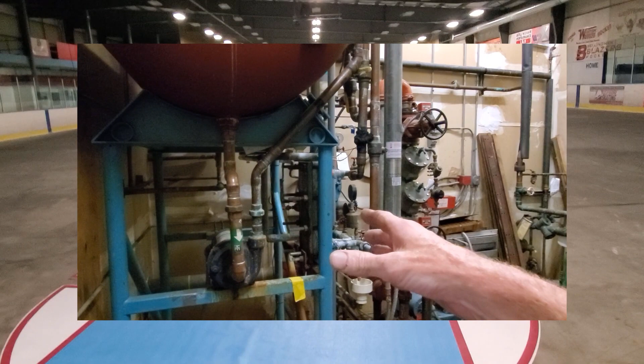The critical numbers were the head temperature and the discharge temperature, as well as the water temperature of the cooling tower, which went from 85 down to 83. That was really good, so we left it running overnight.